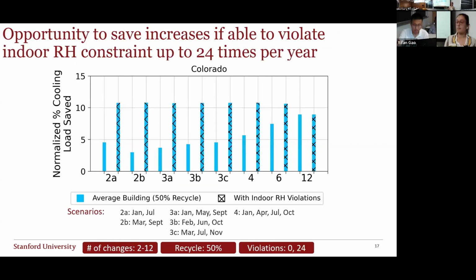We can also look at the impact of allowing indoor air relative humidity constraints. Again, this is just Colorado as an illustrative example. If we allow 24 violations, we suddenly have much higher savings, and we get the largest amount just by changing it twice a year. That's pretty exciting because twice a year isn't much work, and we see up to a little over 10% savings in this scenario.